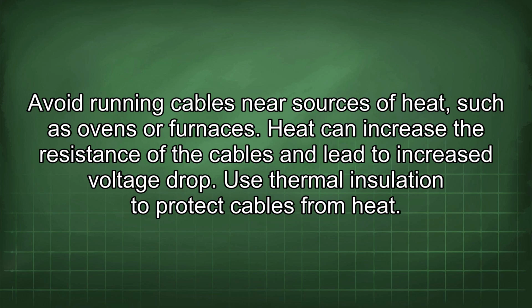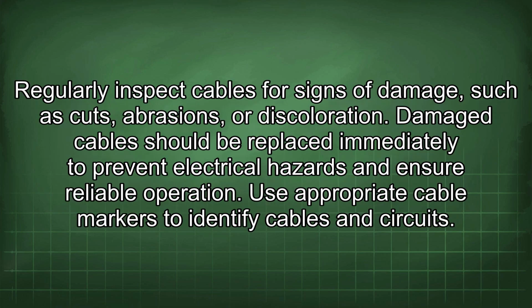Avoid running cables near sources of heat, such as ovens or furnaces. Heat can increase the resistance of the cables and lead to increased voltage drop. Use thermal insulation to protect cables from heat. Regularly inspect cables for signs of damage, such as cuts, abrasions, or discoloration. Damaged cables should be replaced immediately to prevent electrical hazards and ensure reliable operation.